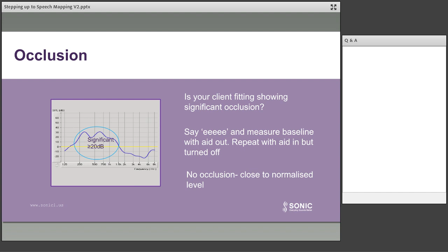Then you put the hearing aid into the ear, turned off, and repeat it again. The yellow line was the baseline without the hearing aid in, and the purple line shows what happens just when you put the earmold into the ear. Wherever there's a difference of 20 or more, we can say that there is significant occlusion happening in that ear.